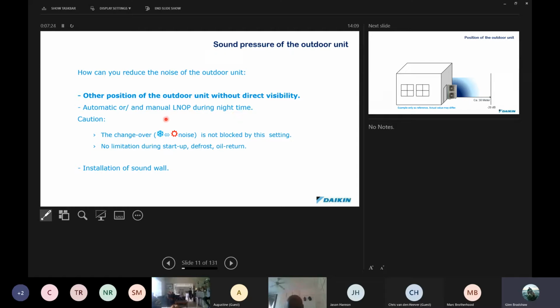The other way is that we've got a low noise board. That board plugs into the condenser, and then by closing certain contacts on that board, we can initiate the low noise operation. So it's a more accurate way of doing it. But both of them work pretty well, and we've used them with success on many jobs. Something just to remember when using low noise operation: the unit has to go through certain functions. These functions cannot be avoided. For instance, the changeover sound from cooling to heating, the swishy noise you get through a four-way valve, that you cannot do away with.